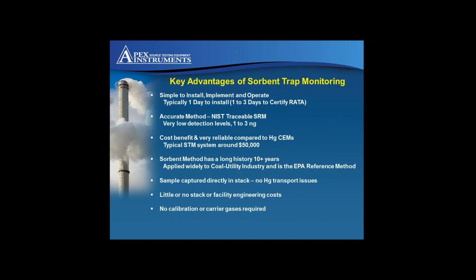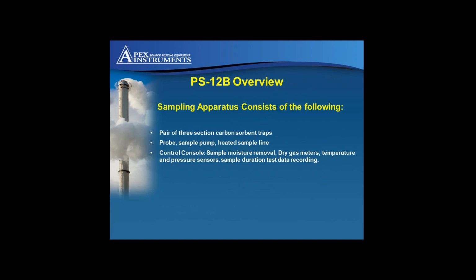If we look at the key advantages of sorbent trap monitoring, a system is quick and easy to install, and importantly, no calibration gas requirements. The system is certified by a RATA test using a Method 30B system, but a sorbent trap monitoring system offers a significantly lower cost option for demonstration of regulatory compliance. So, a pair of 3-section sorbent traps sampling continuously for typically 7 days. The system comprises a dual trap probe, sample pumps, heated sample line, a control console, sample moisture removal, and high integrity test data collection.